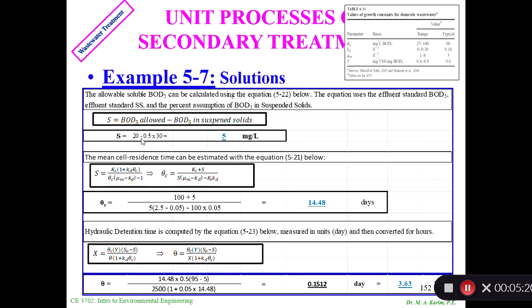The mean cell retention time using equation 5-21, we know this equation, and if I put the values I get 14.48 days. Then hydraulic retention time equation 5-23 can be calculated using this equation. If I put the values, ultimately I get 0.151 days equal to 3.63 hours.